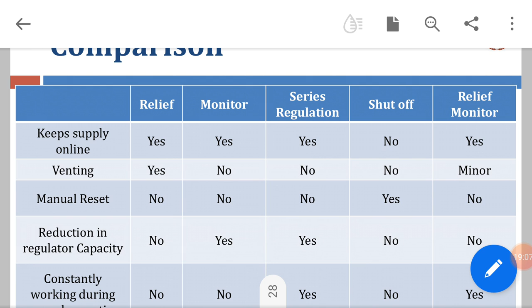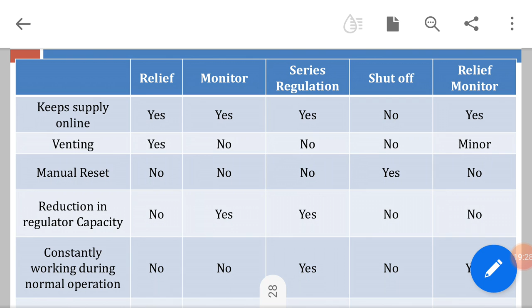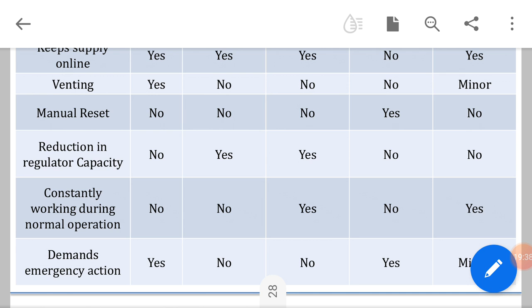Reduction in regulator capacity is no for the first one. We have yes for the monitor and series regulator. For shut-off it is no, and for relief monitor it is no. For constantly working during normal operation, it is no for the first two parameters, yes for the third parameter, no for the shut-off, and yes for the relief monitor.